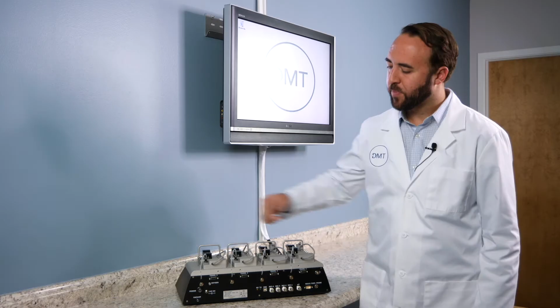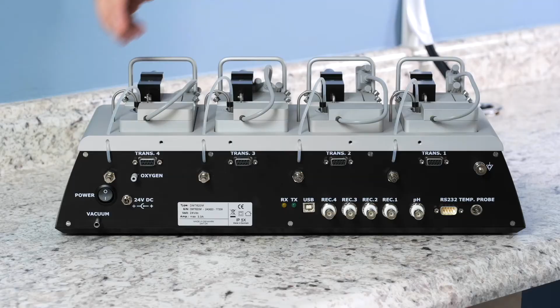The back of the interface has all the connections needed to fully utilize the system. There is a power supply and a power switch. There's a port for vacuum that you can connect to a vacuum source for buffer removal. There's an oxygen port that you can connect to a carbogen tank or any other mixture that you would like to use to bubble your chambers.